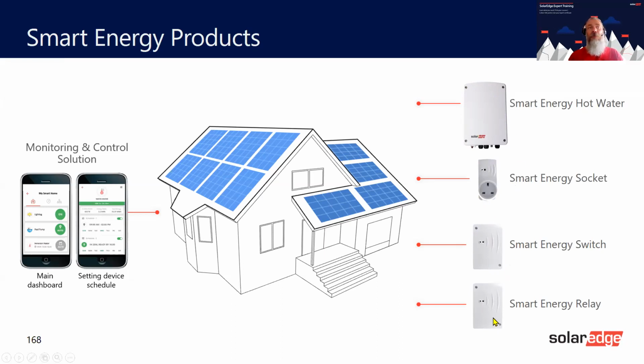The smart energy relay is used to control heat pumps. Two relay settings in it, so you can control other devices, much larger devices. You can use the smart energy relay to switch a contactor. You can then switch whatever load you wish. The smart energy switch, as such, is a hardwired device. This is a plug-in device. This is a hardwired device.